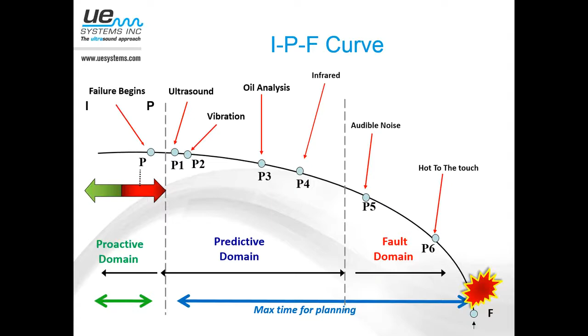Some typical applications, again, I mentioned this: compressed air and gas leak detection. Anything under pressure will create turbulence, and ultrasound can detect the source of that turbulence very quickly and very accurately. We can detect vacuum leaks, in other words, leakage that's being pulled in, very easily. And it's a non-intrusive method for leak detection. In other words, you don't need to use any kind of surfactant or fluid. It's strictly based on hearing the turbulence at the leak site.